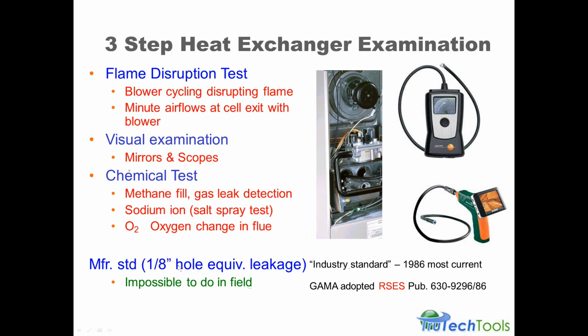And then finally, the manufacturer standard, basically, to the best of our knowledge, is about a 1/8 inch hole is allowable for equivalent leakage in a heat exchanger. They don't feel they can get any tighter than that. And this is an impossible test to perform in the field. So some of these intermediate tests were developed, and some of them were published in a GAMA, which is the old Gas Appliance Manufacturers Association, and a RSES, or a Refrigeration Service Engineers publication in 1986, if you wanted to reference that.